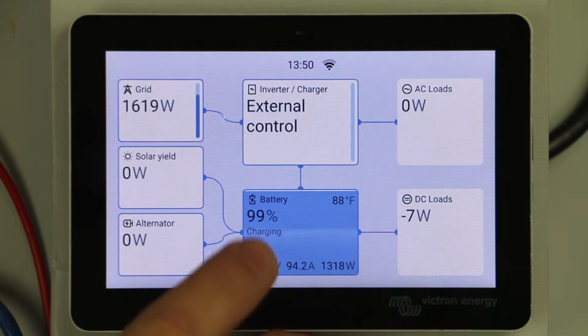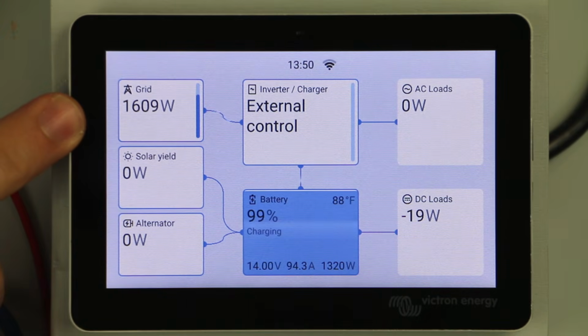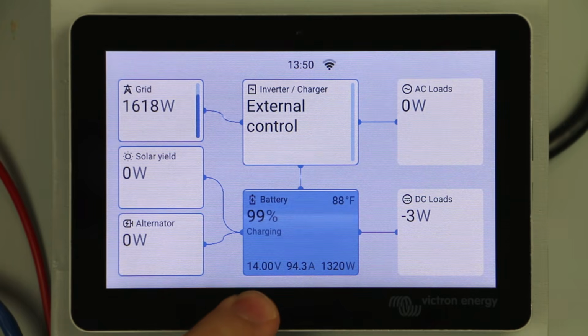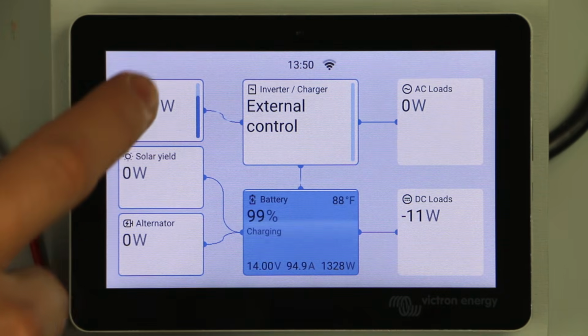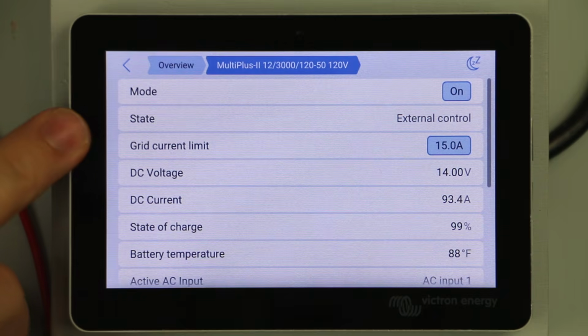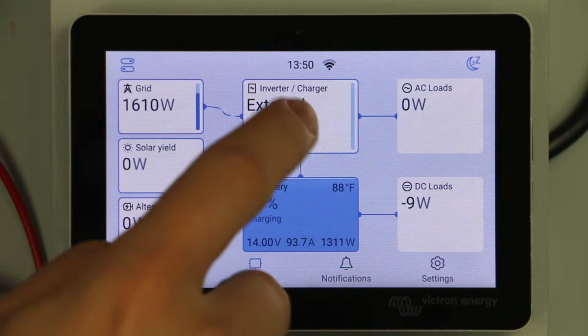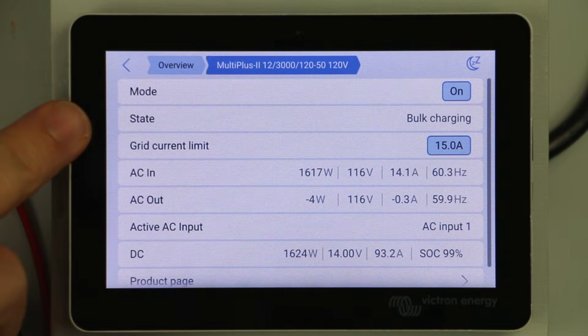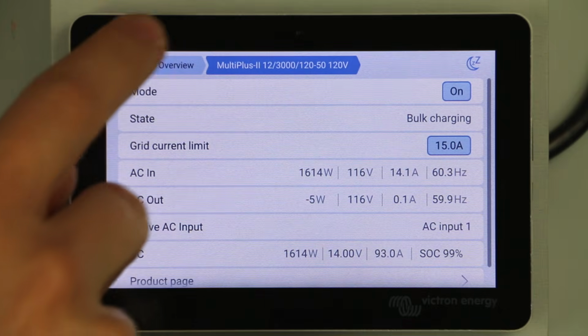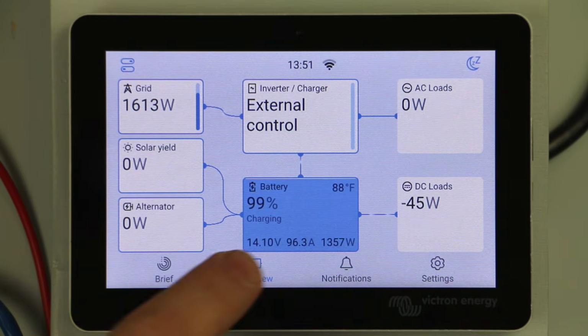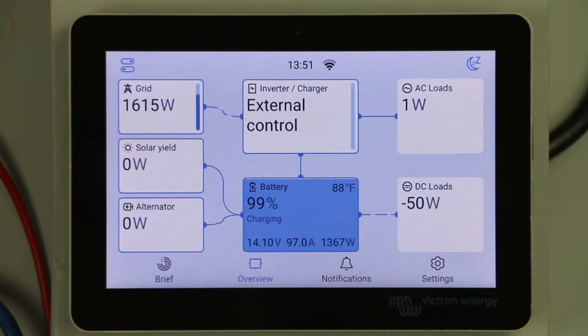All right, we're at 99%. You can see I've just got the shore power charger going, and we are at 14.0 volts. So we're getting there, and we should be going into the absorption phase in just a second. If we click on this, it may tell us that it's in bulk mode. It'll say external control, but if we click here, state says bulk charging. So in just a minute, when it hits 14.2 volts, it's going to switch to absorption mode, and it's going to hold that for 30 minutes, 15 minutes per battery.